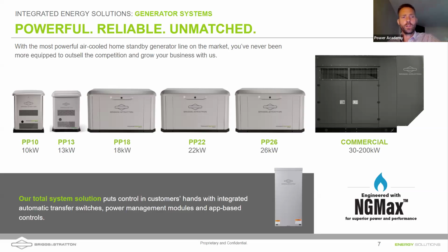And one of the nice things about generators is that they have almost an unlimited runtime, unlimited fuel supply in the event of an outage. So as long as you've got a large fuel tank, like a large propane tank, or if you've got access to natural gas, these, what you're seeing here on the left side, are the air-cooled generators from Briggs & Stratton for home backup. And these are engineered with what we're calling NG Max, which allows, there's actually no derating when you're running these things off of natural gas. So the 26K generator will truly give you 26K off natural gas, unlike many of our competitors where there's a derating due to the lower energy density of natural gas compared to propane.